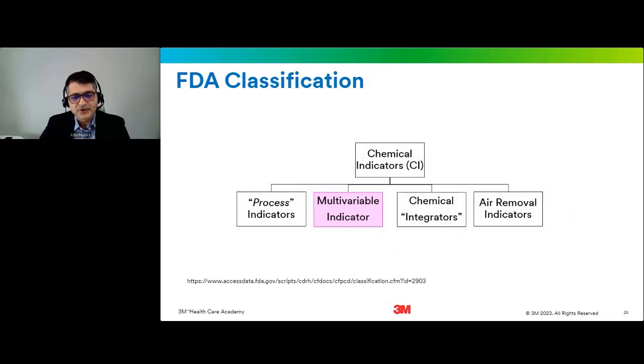As I mentioned in the previous slide, the FDA classification is different. FDA has its own separate classification from ISO for chemical indicators. The chemical indicators were initially divided into process indicators, chemical integrators, which is similar to type 5 in steam, and air removal indicators, that's the Bowie-Dick test.